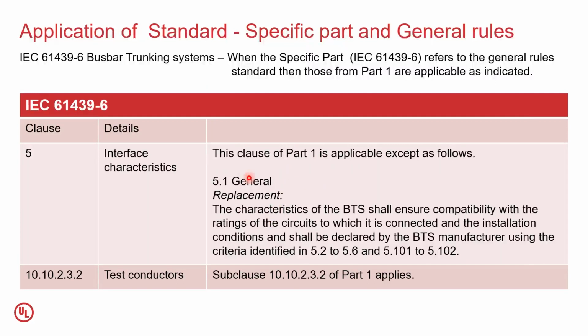So you need to replace the general statement there, and it says the characteristics of the busbar trunking system shall ensure compatibility with the ratings of the circuits to which it is connected and the installation conditions, and shall be declared by the BTS manufacturer. So this is a replacement. You need to replace this clause from part 1 and use it while you apply the standard.